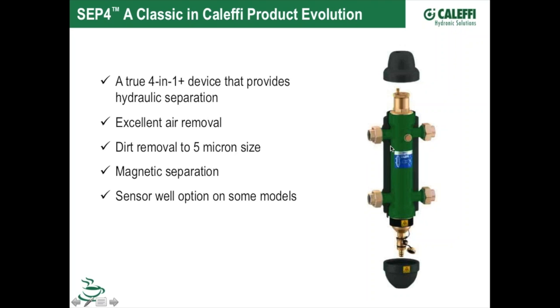So now your boiler is looking at this separator, this device, this vessel, this capacity, this amount of water in the system, plus all the piping between the boiler over here and the device. Now that's the load that the boiler sees. So every time the boiler kicks on, it's seeing this whole content in there. So a lot of guys like to put their sensor in there and use that as the operating point. Most of the new boilers out there will have a 6-millimeter diameter sensor that comes with them as an option. If you do want to move it out of the boiler and put it somewhere else, we do have a well that accommodates that 6-millimeter that will go right into that port. So maybe we should change that to a 5-in-1.